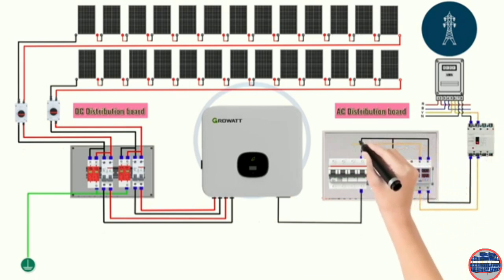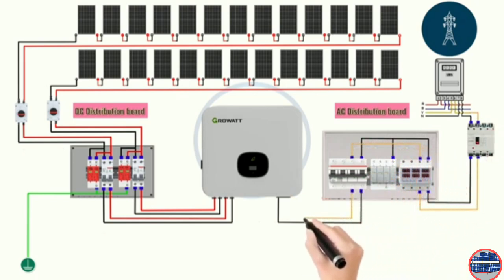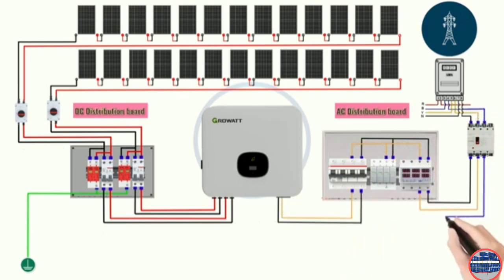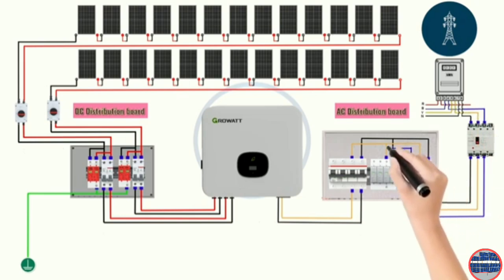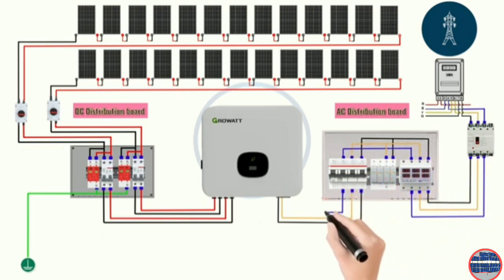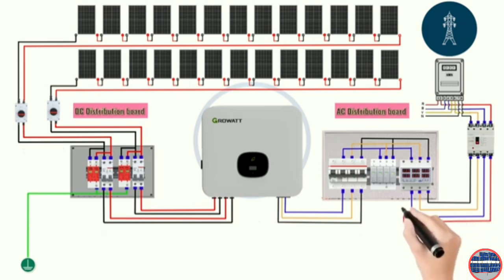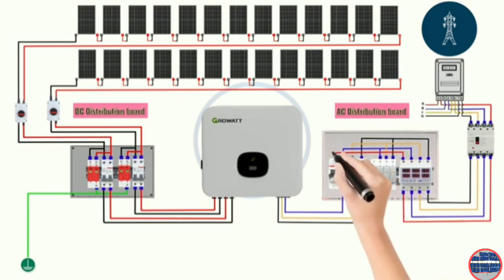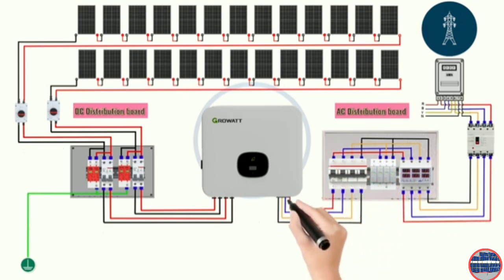The output of the energy meter then goes to the input of our 4-pole 100 amp AC disconnect switch. This switch allows us to isolate the solar system from the grid for maintenance or emergencies. From the disconnect switch, the wiring goes to the input of a three-phase voltage protection relay. This relay safeguards our equipment by disconnecting the system if the grid voltage fluctuates outside acceptable limits. The output of the voltage protection relay connects to the input of the AC surge protective device, or SPD. The SPD protects the system from voltage surges caused by lightning strikes or other electrical disturbances.